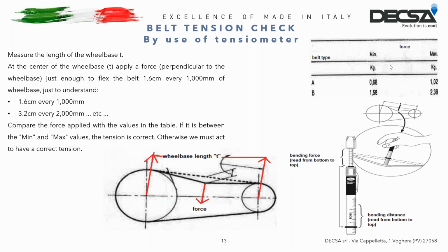Currently, the belts we install are single-backed with as many inserts as there are pulley grooves. This solution is more effective because a single belt does not fall even if it's loose. Therefore, the tension values must be multiplied by the number of inserts in the belt. For example, with a 3-groove pulley, the values are multiplied by 3, with a 4-groove pulley by 4, and so on.